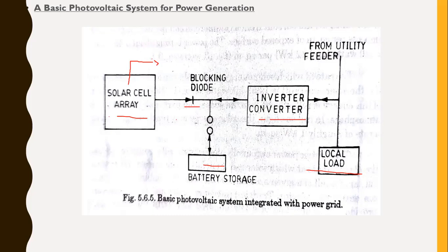Without a blocking diode, the battery will be discharged back through the solar array during the times of no insolation. We discussed this before with the solar cell equivalent circuit for a forward bias diode, in previous figures.